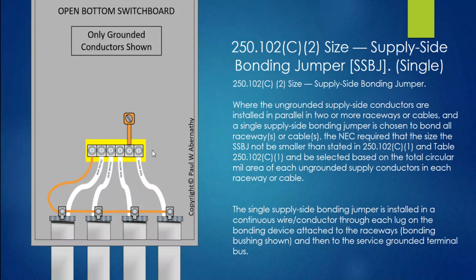We have to take 2,000 kcmils and do that times 12.5% because it is over 1,100. Okay? And we are using copper unless stated otherwise. If that's the case, this would result in a rather large supply side bonding jumper. Now, chances are, if you've ever done this before, you're going to see that these lugs handle wires, whether they're lay-in or feed-through, up to a certain size, and then they can't handle anymore. And you certainly don't want to use the wrong lug for the application.